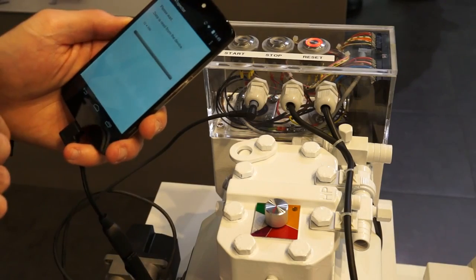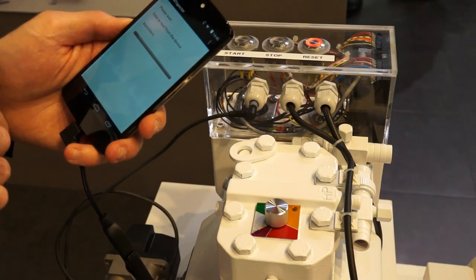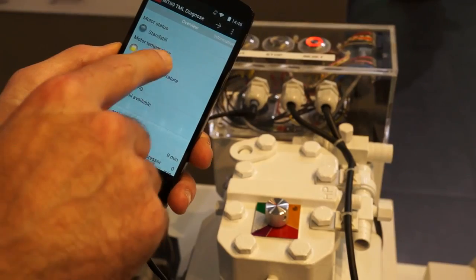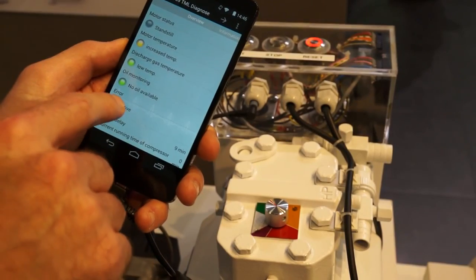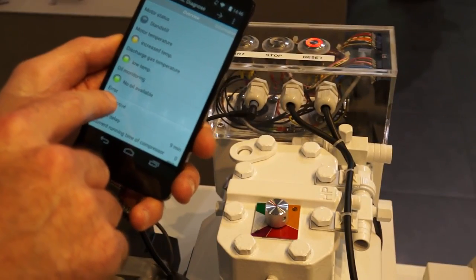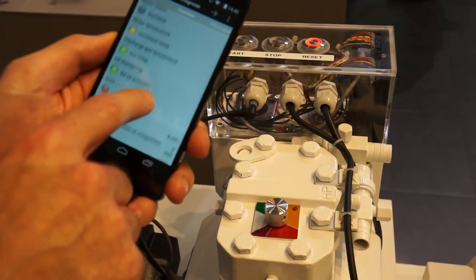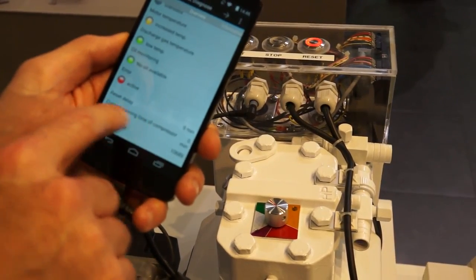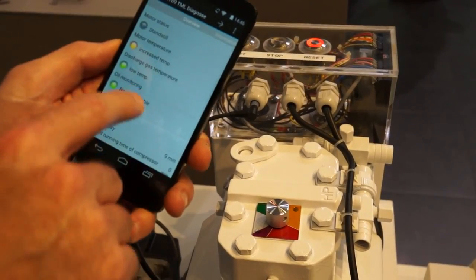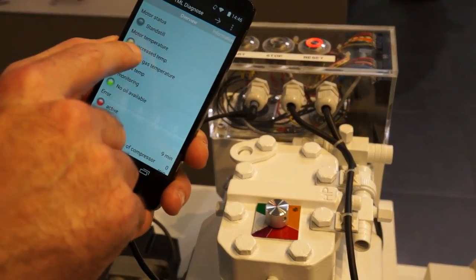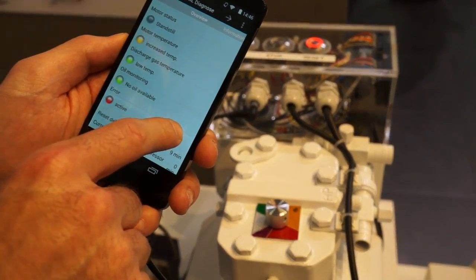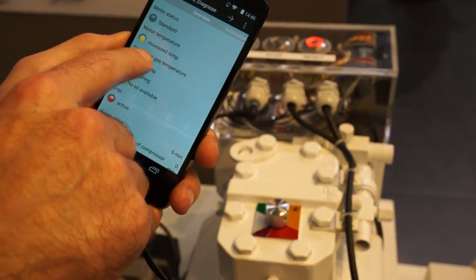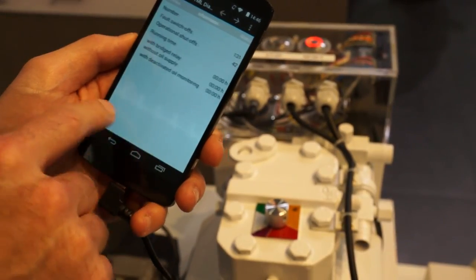The app starts automatically and the data is read out. As you can see, the motor has stopped due to an error and there is now a 9-minute delay. The cause is an excessive discharge gas temperature and there is also an increase in the motor temperature.